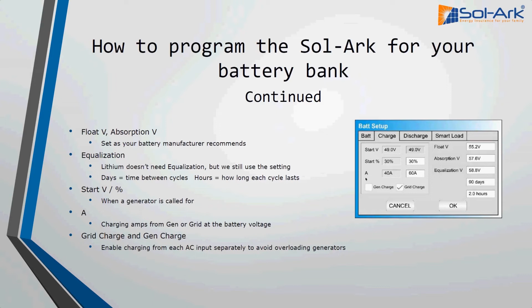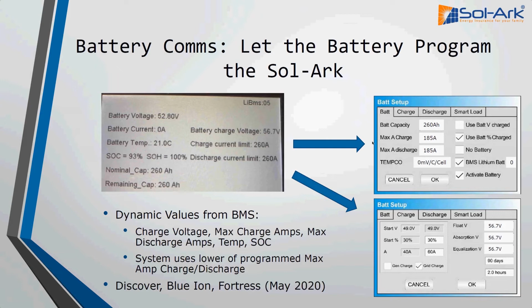All right. So, battery communications. This is an example of the information that we can get from a battery's BMS. Stuff like charge voltage, max charge amps, max discharge amps, temperature, state of charge, and these are all dynamic values. So we're getting these from the BMS basically in real time, which is cool. And the battery can basically tell the Sol-Ark to change its own settings also in real time. So here, for example, we have the BMS lithium battery selected because we have a BMS that's trying to talk to us, and it's also a lithium battery, so we've changed this to 0 millivolts per degree C per cell, and so on. And the battery is actually capable of changing the float, absorb, and all that stuff as well, so that's pretty cool. Now, like I said, Discover Blue Ion Fortress should be coming here in May 2020, so that's pretty sweet.